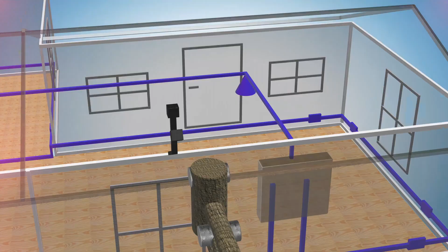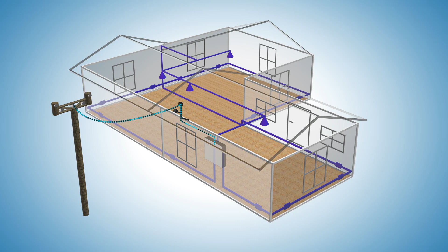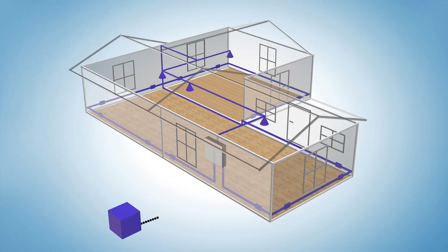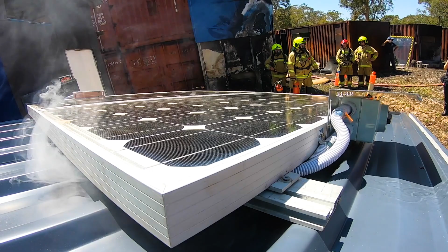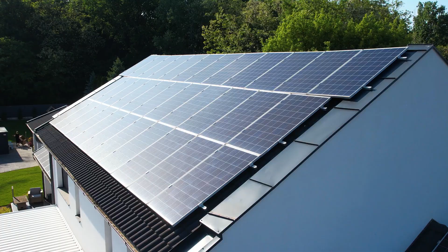Just because the main power switch is off does not mean the site is electrically safe. There is still a possibility of an explosion or electric shock, because the conductors are still live between the supply point and the switchboard. Additional risks may exist if the property has embedded generation from solar systems. Check the property to see if solar is present, as these systems will continue generating electricity.